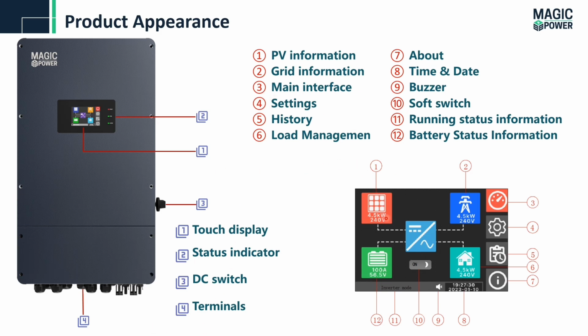If we look at the touch screen, what we can see is the PV information, the generation information, what the PV generates, the battery information, the grid information, and the load side, like how much load is connected to our system. Here we can see the main interface, the settings, and similarly the history. In the history we can see the alarms and warnings, the information of the system, and the inverter mode, at what mode the inverter is working at that time. So these are some icons which we can see on our touch screen.